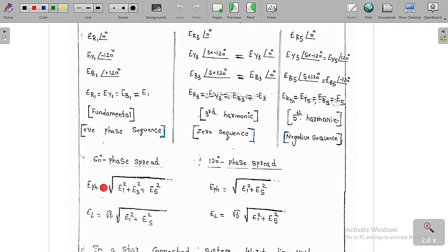So here the phase voltage is equal to root over E1 square plus E3 square plus E5 square, and the line voltage is root 3 times the phase voltage. Here you have to remove the third harmonic component, so you are going to get it in this manner. Again, for 120 degree phase spread, you have to remove the third harmonic component, so E phase is equal to root over E1 square plus E5 square, and EL is equal to root 3 times the phase voltage. Just take root 3 times the phase voltage, and you are going to get it in this format. So clearly this is for the 60 degree phase spread and this is for the 120 degree phase spread. These are the important formulas that you always have to remember.